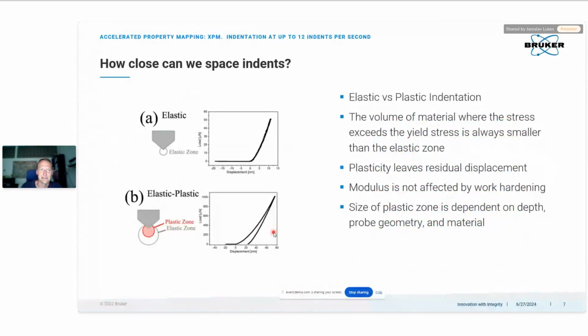The most basic question that I usually get is how close we can get the indents together, and what is basically the resolution of such a map. Right, so you have to think about what the output is and what you are interested in. If you are interested only in the elastic properties, you have more freedom. If you are interested in the absolute values of the hardness, it is a different story. Let me just remind you: if you do a very shallow indent in the elastic regime, the load and unload go along the same line. You create an elastic zone under the indenter, and if you unload, there is no residual indent, there is no residual deformation.